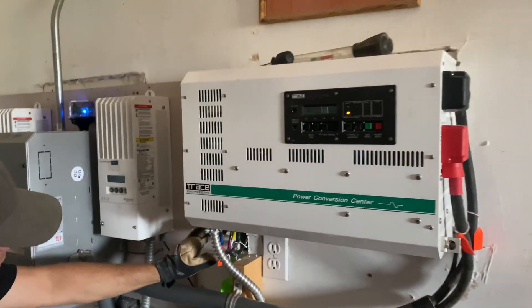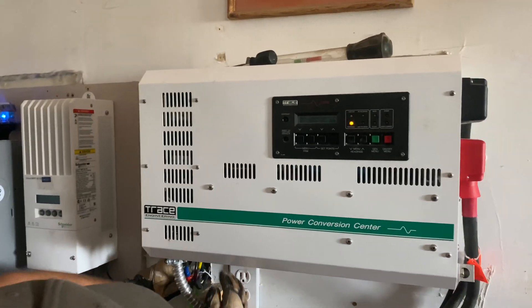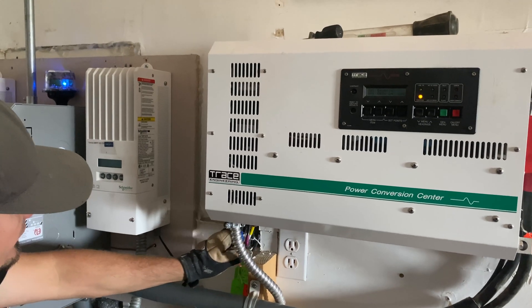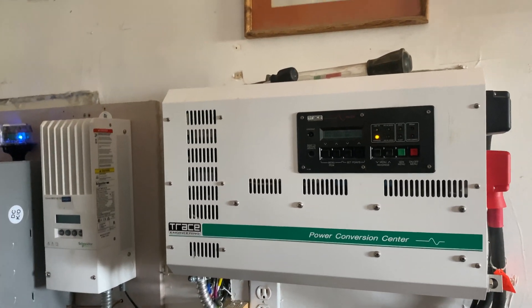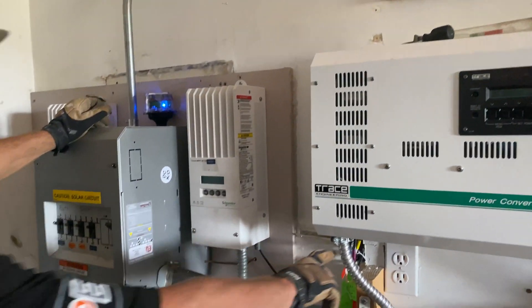None of these wires were really identified, so I identified all of them. I didn't wire this — it was done back in the 90s. Interesting how this THHN does not complete itself through flex; they just put it in the wall and drywalled. That's how they did it back then. I don't know how it passed inspection, because we always have to terminate with flex.